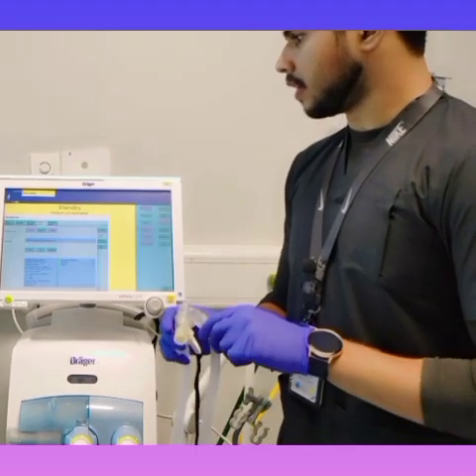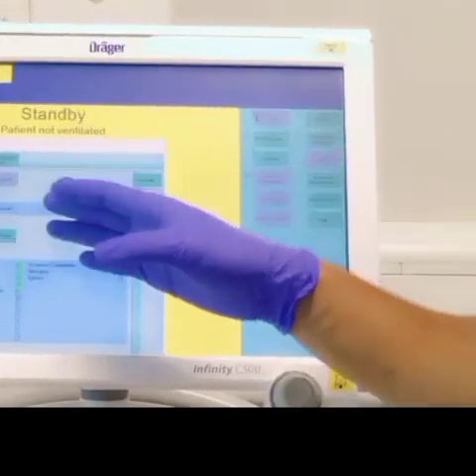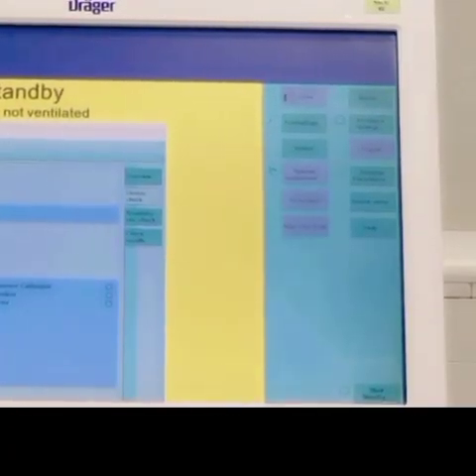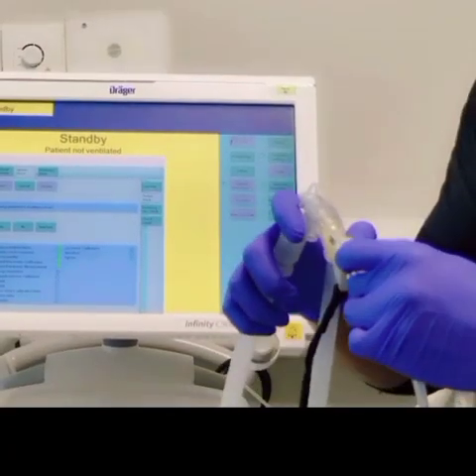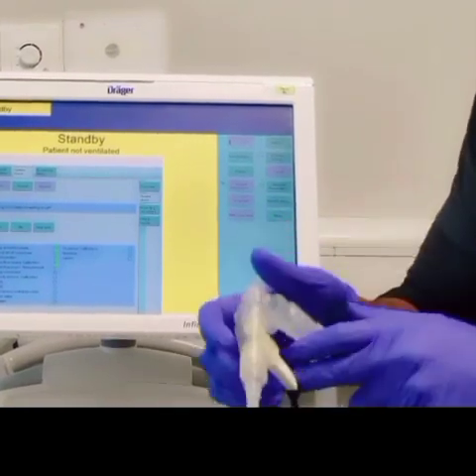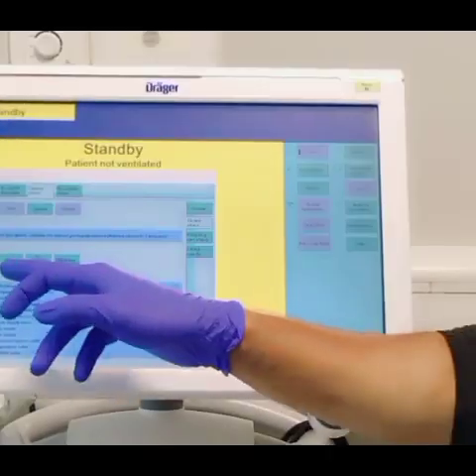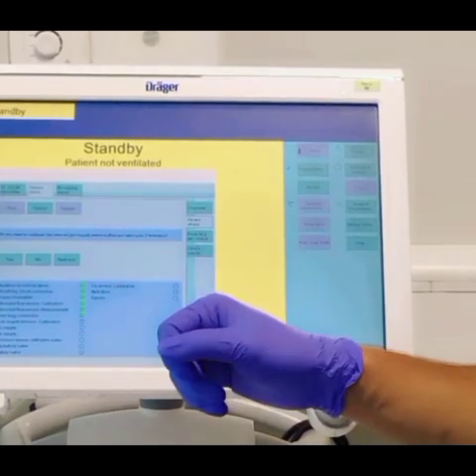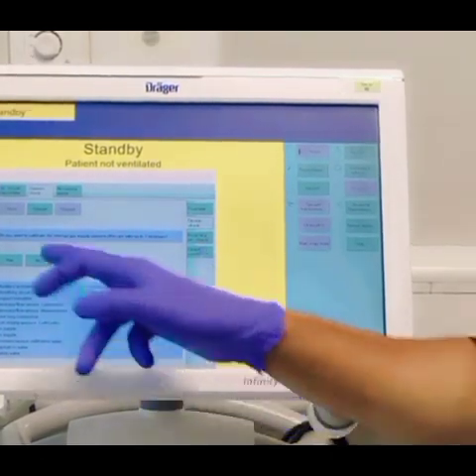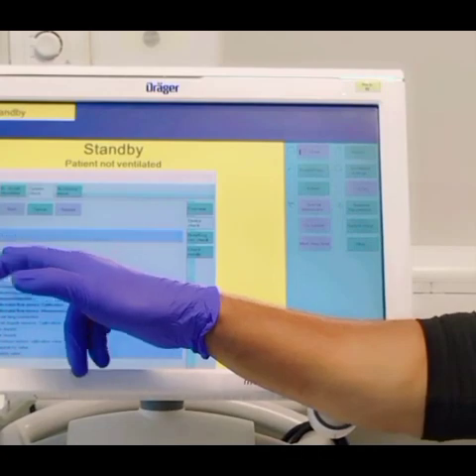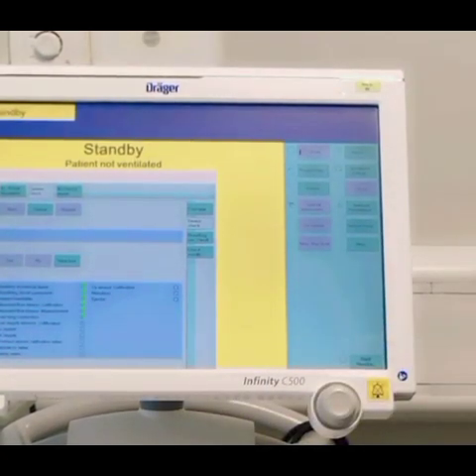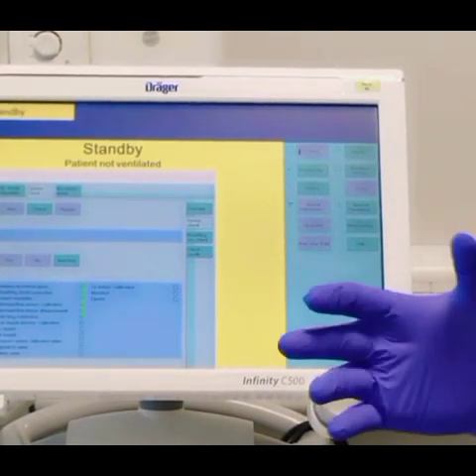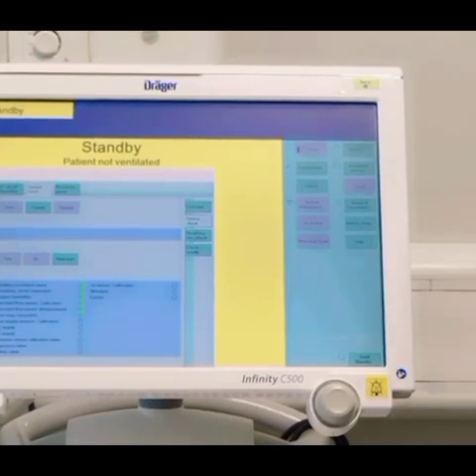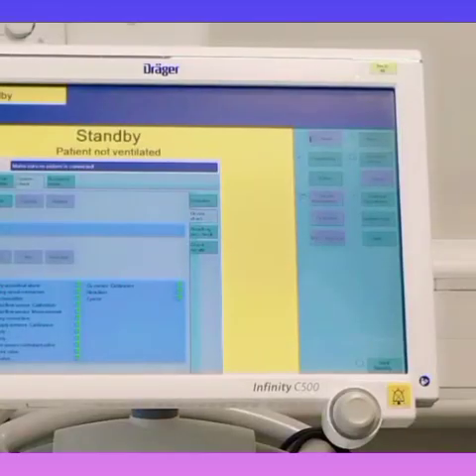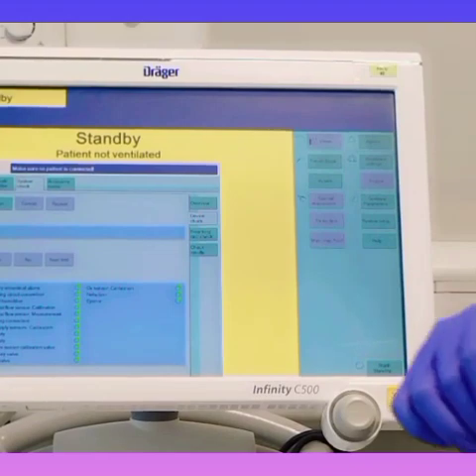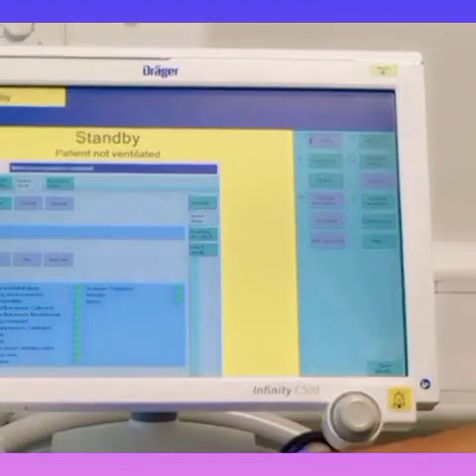So the next one is test lung connected to breathing circuit. Test lung here should be connected with the flow sensor. So the next step is the calibration of gas supply sensors. We have to press yes. It will take around 2 to 3 minutes. So as you can see, our device is calibrated.